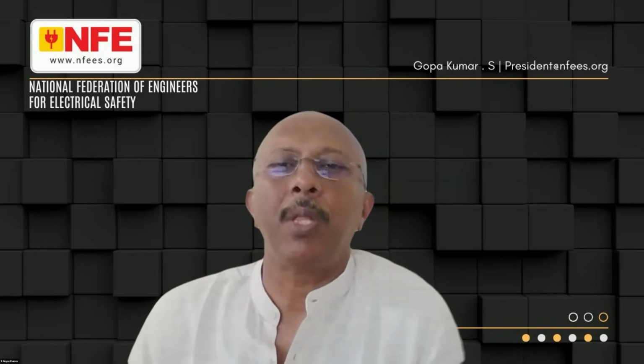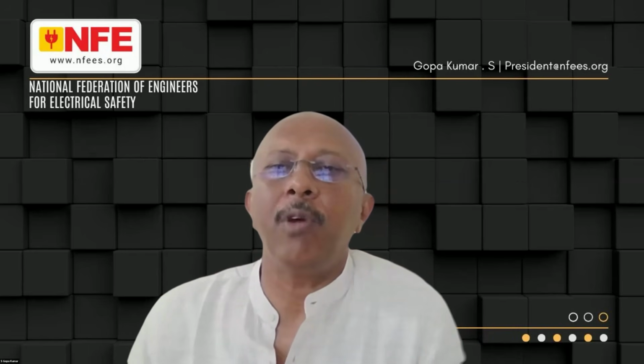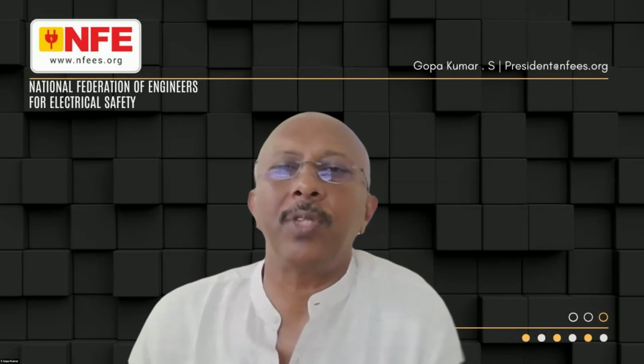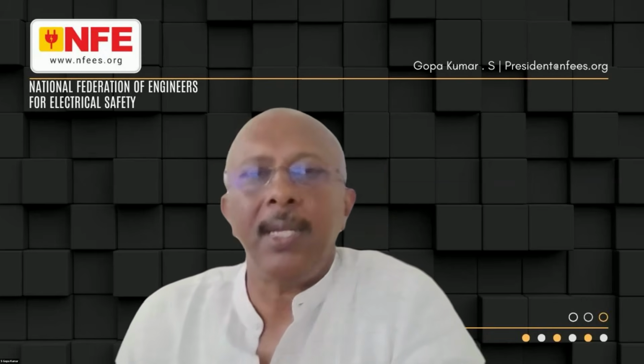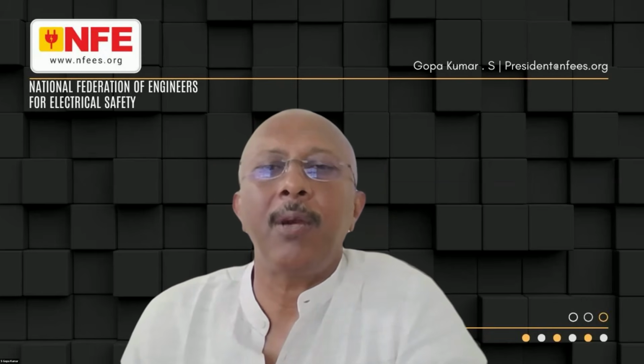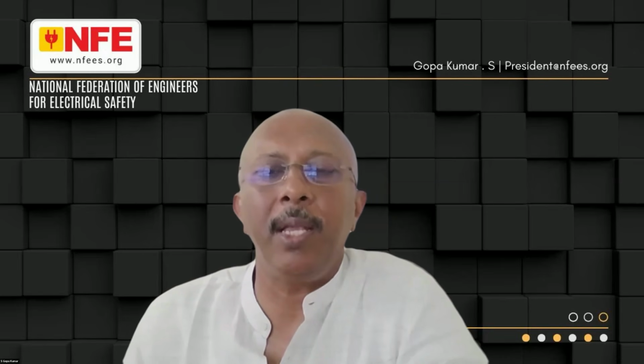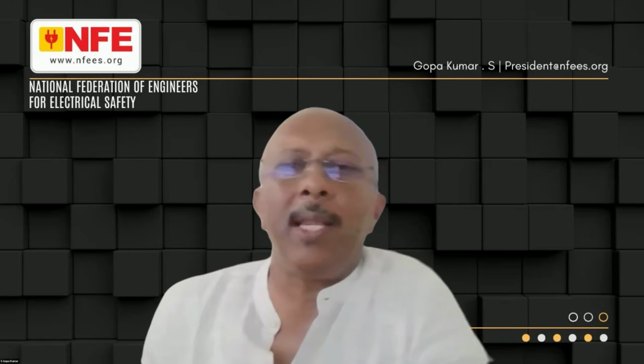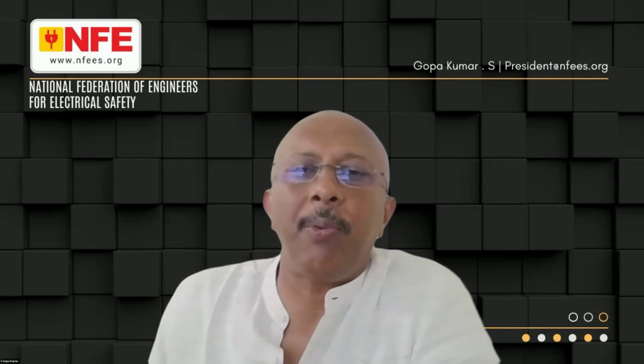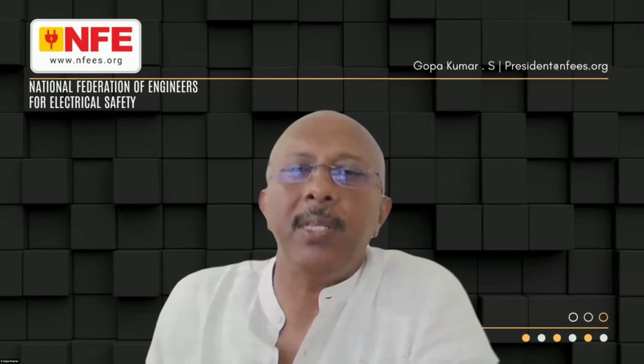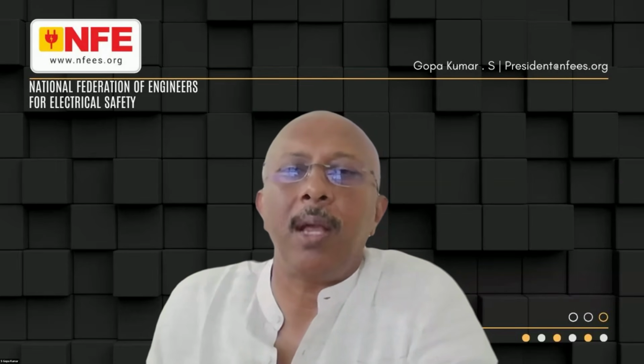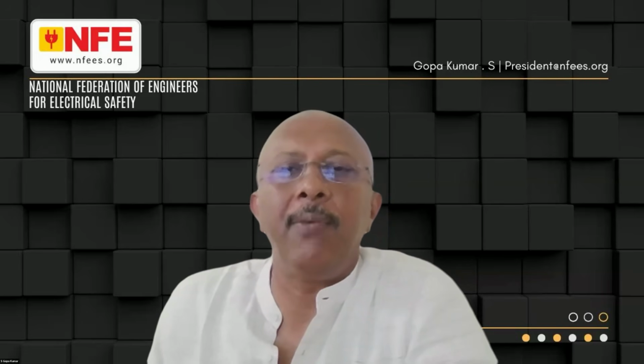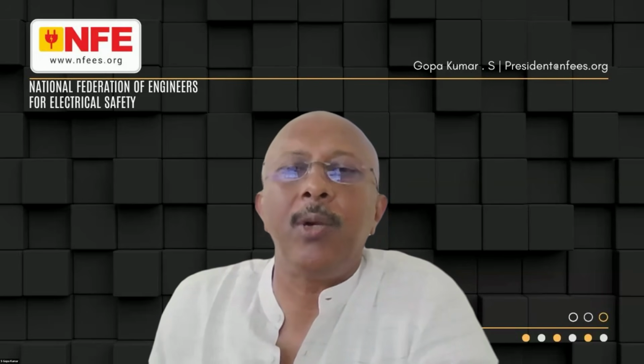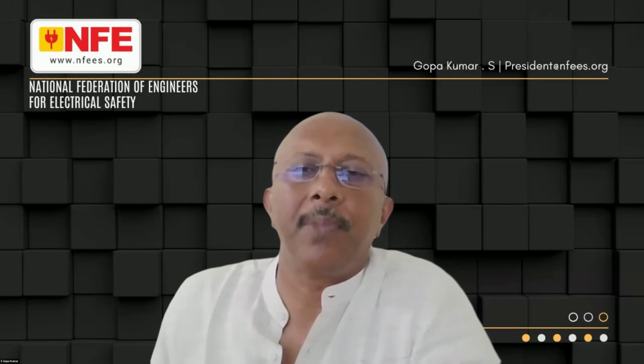Question from Mr. Subrata Bera. Is separate earthing required for solar power systems and processing instruments to ensure electrical safety? Mr. Bera, please understand that separate earth electrodes are absolutely not required for any requirement. It can be biomedical equipment. It includes biomedical equipment, different sources, solar PVs, lifts, UPS. Separate earth electrodes are absolutely not required. Everything must be commonly connected to one earth busbar.